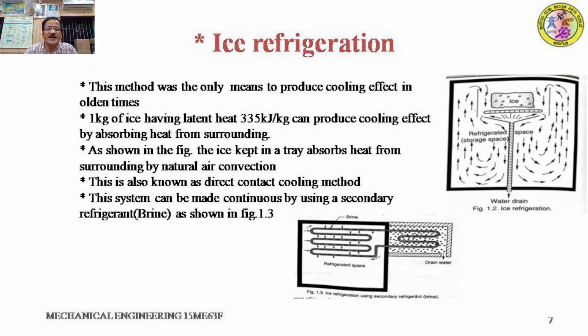It is a tedious process and not convenient. Somewhat it can be made automatic by using a secondary refrigerant. You know that water freezes at 0 degrees centigrade and becomes ice, and below that it cannot stay liquid, but it can be kept liquid by adding salt substances such as sodium chloride or calcium chloride. When these salts are added to water, the solution is called brine, which in technical terms is called a secondary refrigerant.